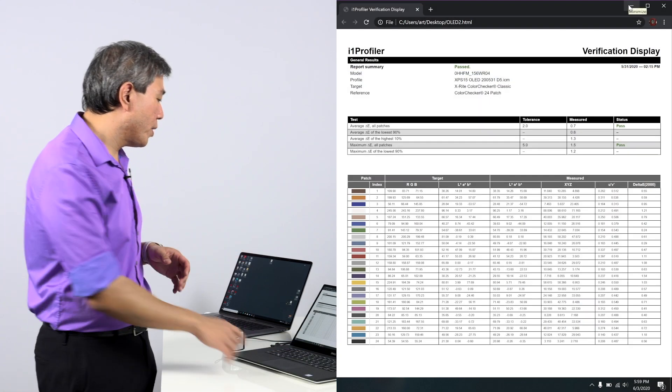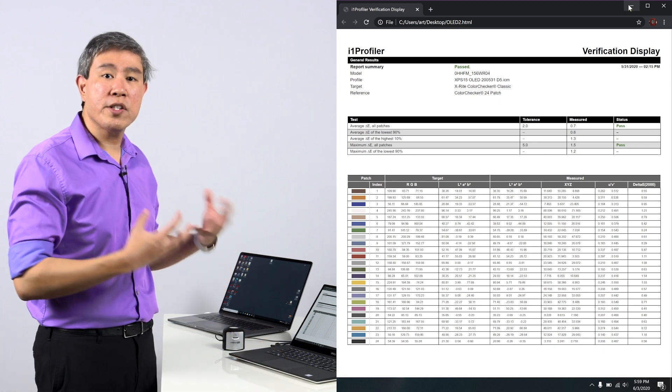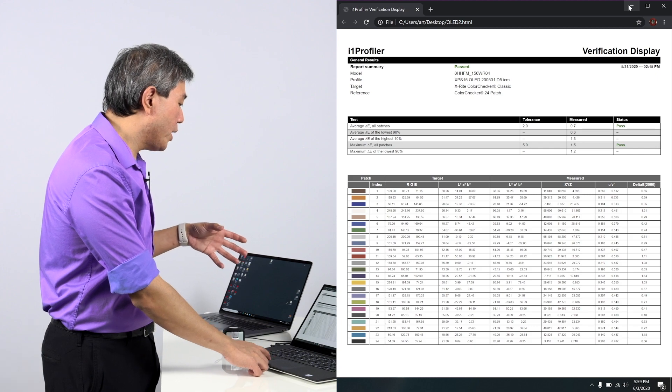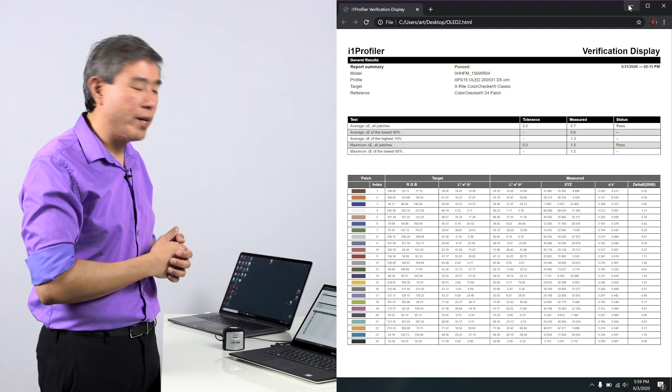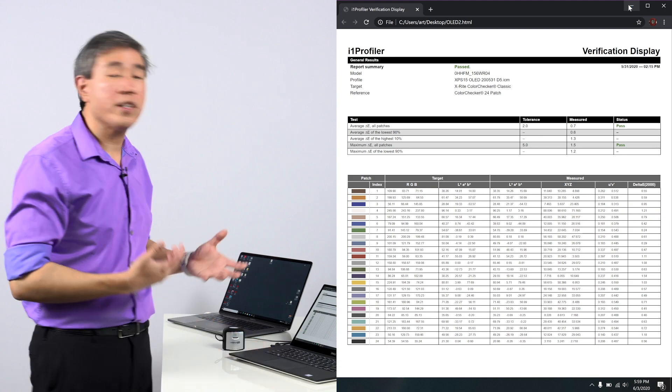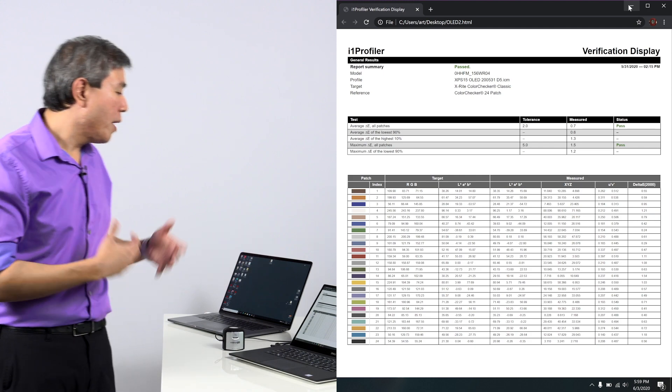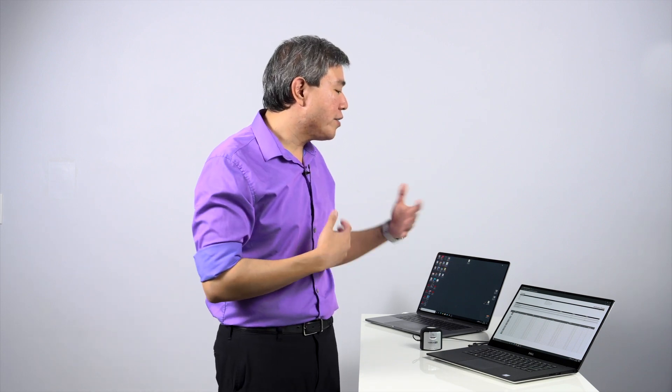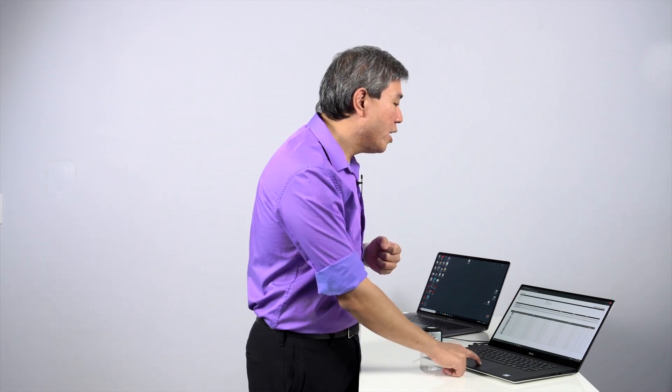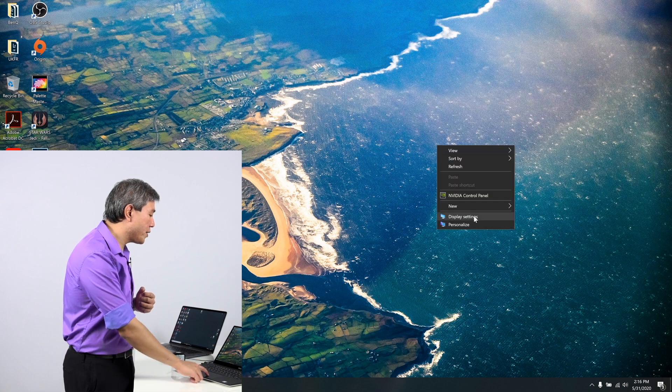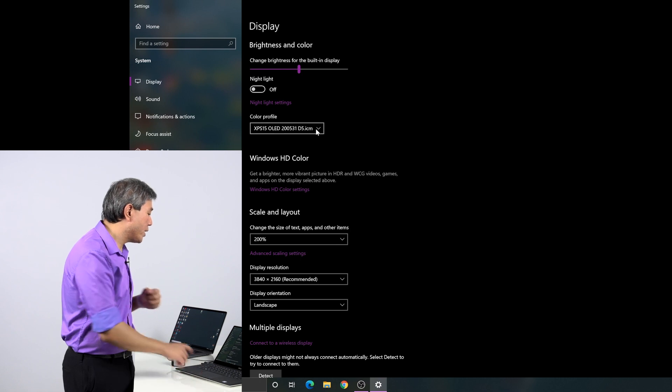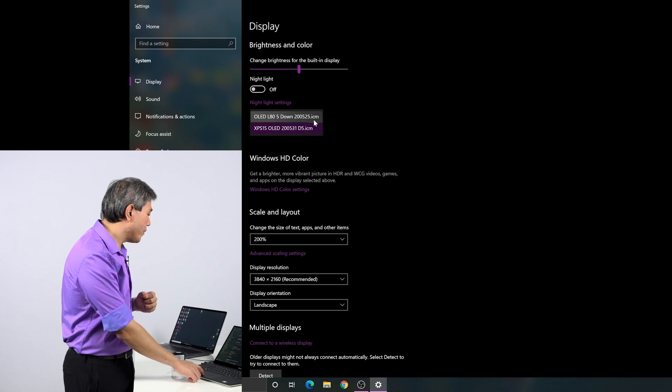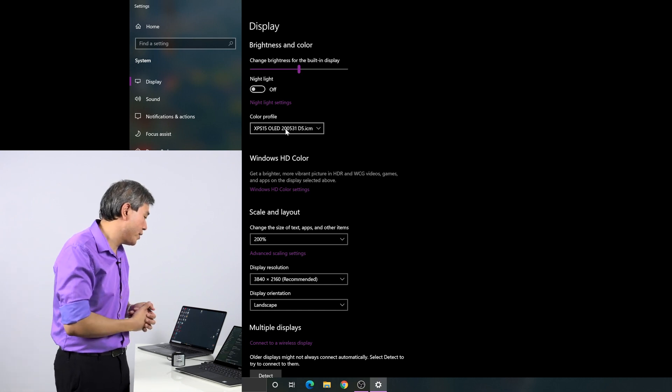This is what the i1 profiler report looks like. It's a summary of the screen we just saw with the measured value, the max value, and it also gives you the actual RGB and lab color readout. It also gives you the delta E for each of the specific color. Very similar to in the program, just in a tabular format makes it easier to see the data. One more thing: when you're done with the calibration, where you save the ICC profile, the moment you have done that, the system has already set the ICC profile for display, so you don't really need to go in and set it again. But if you want to double check, you can do a right click on your desktop display setting. Under color profile, make sure that is the correct one that you have just set.